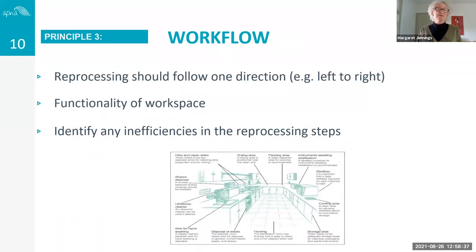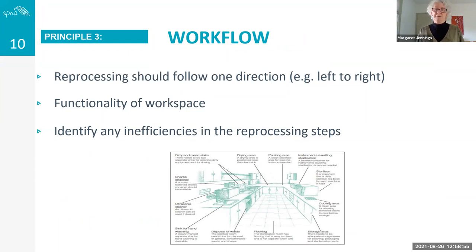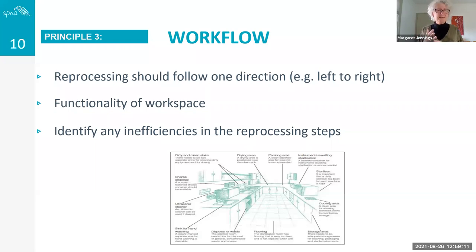The recap shows reprocessing happening left to right. I rarely see practices with four benches available, but if you're reviewing your space, beg for a dedicated space — not shared with the linen trolley or boxes of gloves. This room should look bare. Managers often say there's not much in that room, but it must be low-dust, low-traffic, with a good-fitting door. Nothing extra belongs in there: no linen skip, no waste bins, no boxes.